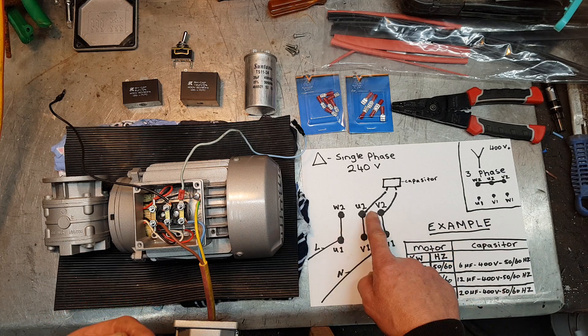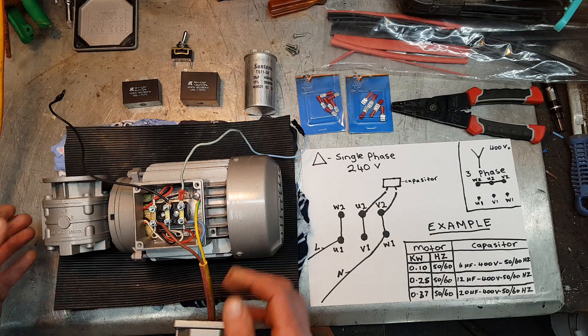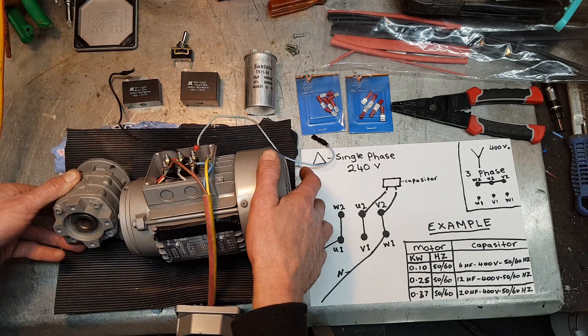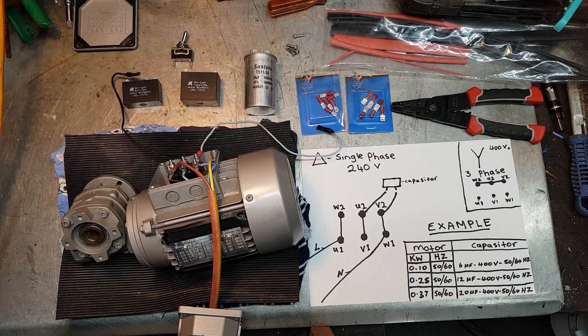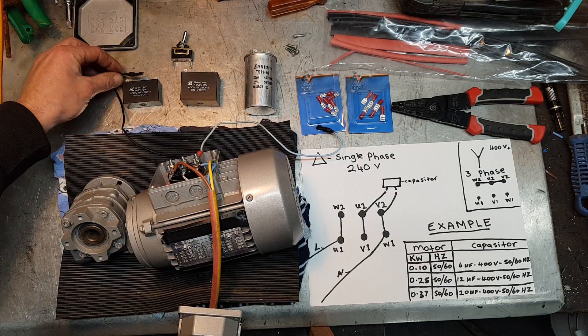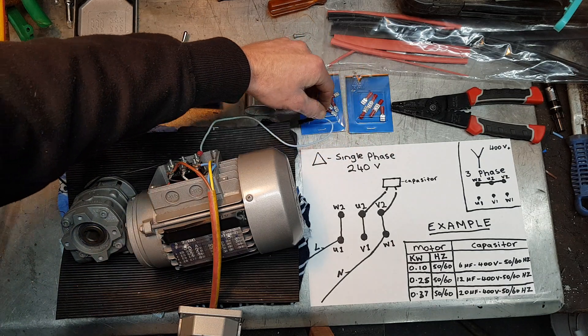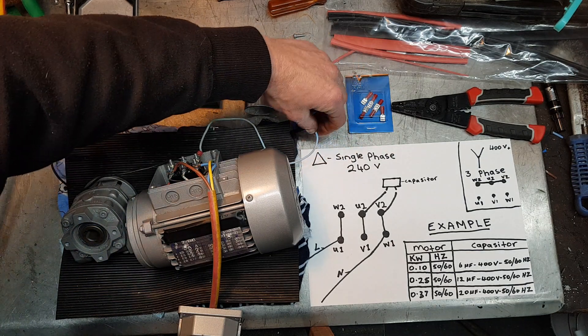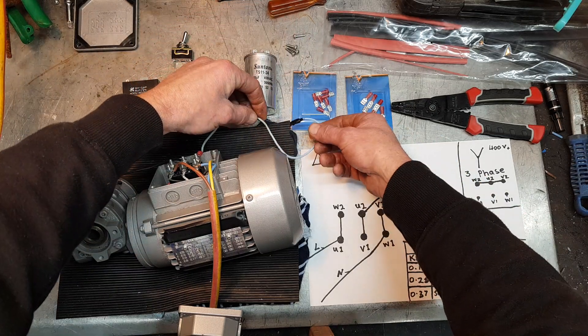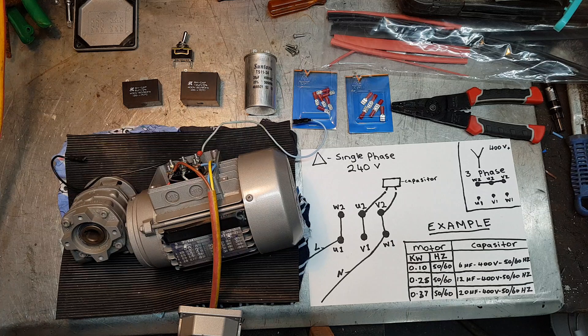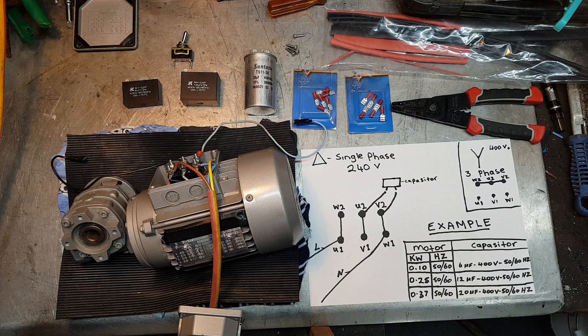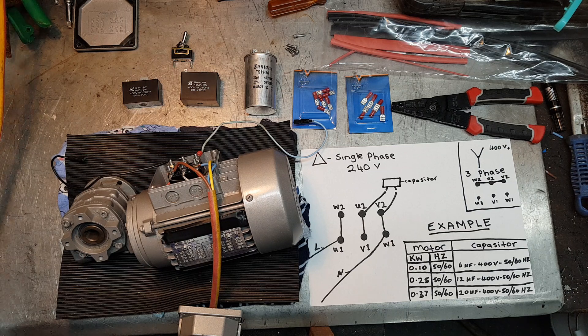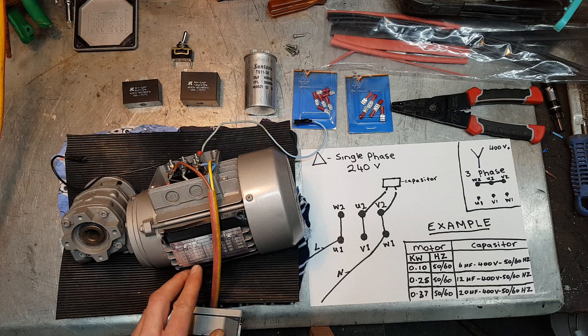I've now wired it to this 240 volt. I'll throw it on the side so you can see the gearbox side of it, and I'll turn the power on, just by itself, 240 volt without the capacitor. Okay, you can hear the motor trying to go but nothing's happening, it hasn't got enough power.